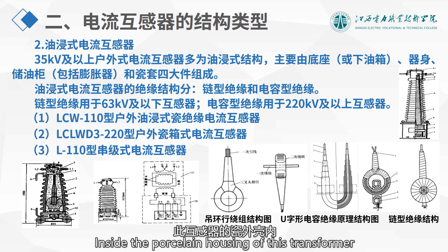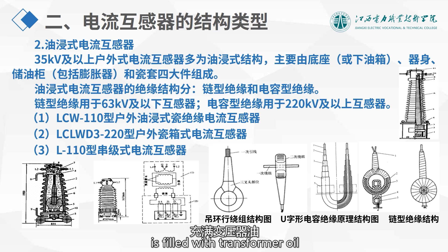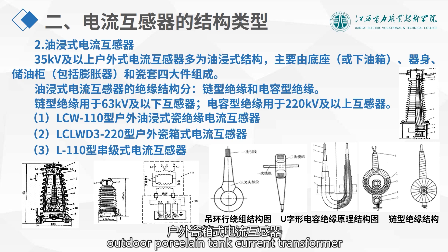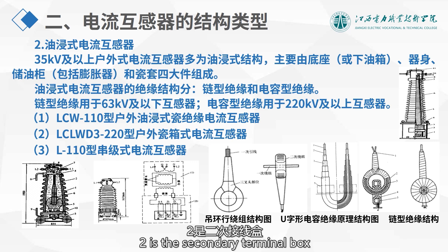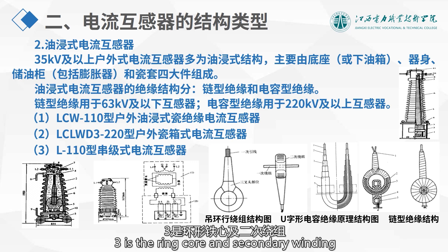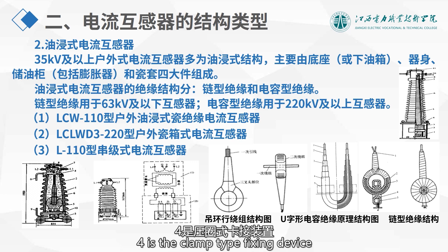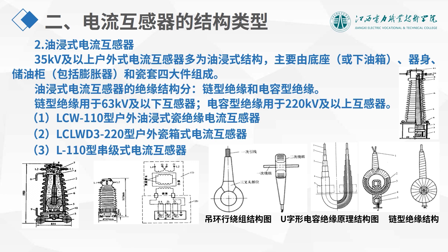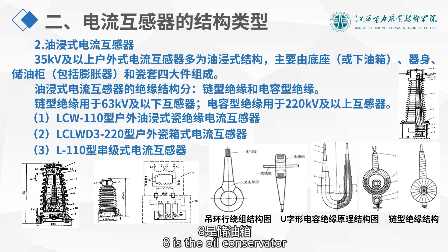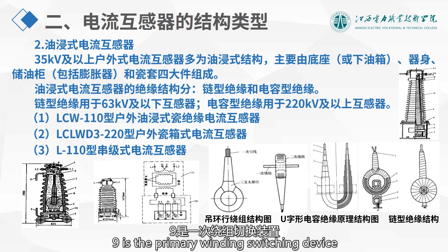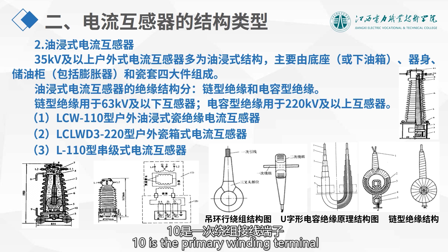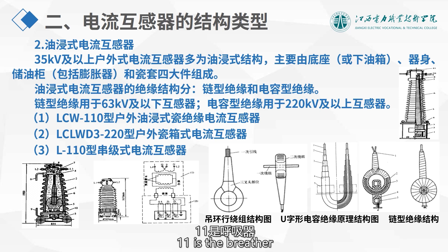Inside the porcelain housing, this transformer is filled with transformer oil and fixed on a metal carriage. The LCLWD3-220 type outdoor porcelain tank current transformer: 1 is the oil tank, 2 is the secondary terminal box, 3 is the ring core and secondary winding, 4 is the clamp type fixing device, 5 is the primary winding, 6 is the porcelain bushing, 7 is the grading shield, 8 is the oil conservator, 9 is the primary winding switching device, 10 is the primary winding terminal, and 11 is the breather.